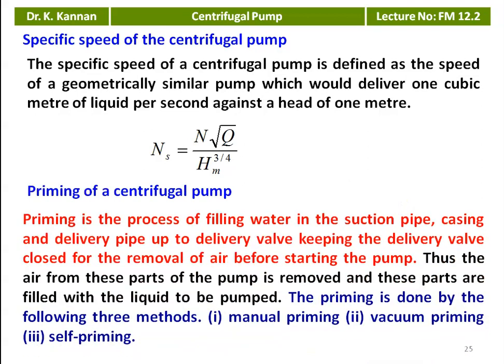Priming of the pump: we discussed self-priming, non-priming, and ordinary centrifugal pump classifications. Priming is the process of filling water in the suction pipe, casing, and delivery pipe up to the delivery valve — keeping the delivery valve closed — for the removal of air before starting the pump. Without priming, if you start the pump, there will be no delivery of water. Air from these parts is removed and they are filled with liquid to be pumped. Priming is done by three methods: manual priming, vacuum priming, or self-priming.